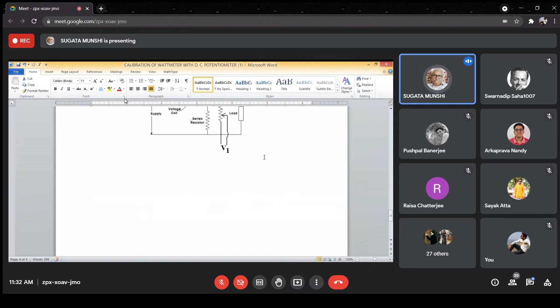this is the potential coil circuit that is supplied from this stabilized DC supply for the voltage circuit. So it is supplied at 100 volts, the rated voltage of the wattmeter. And this current coil is supplied from a low voltage source. So if you have a voltage around 100 volts here, then in this current coil circuit, if you inject a current of 0.2 ampere by adjusting this rheostat, what will happen? The wattmeter reads the current through the current coil multiplied by the voltage across the potential coil circuit. So voltage is maintained at around 100 volts. Now if you make the current 0.2 ampere, the wattmeter will read 20 watts.